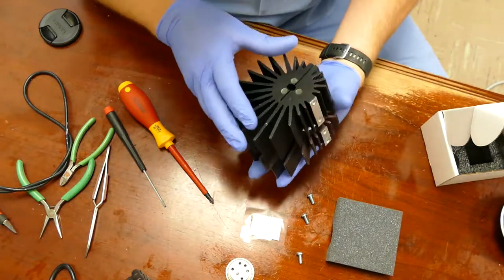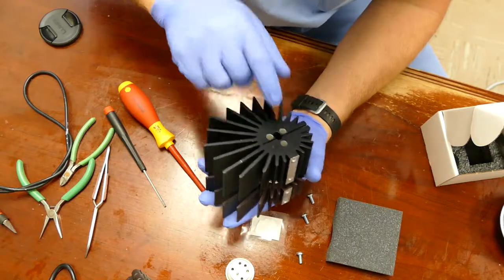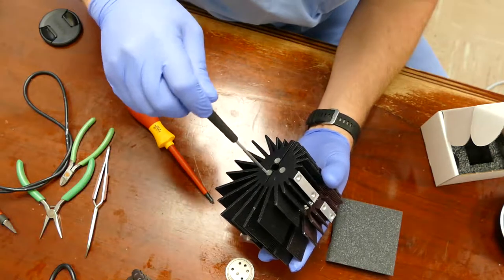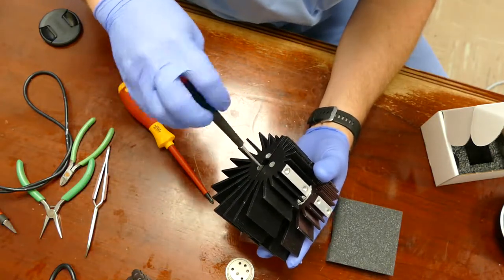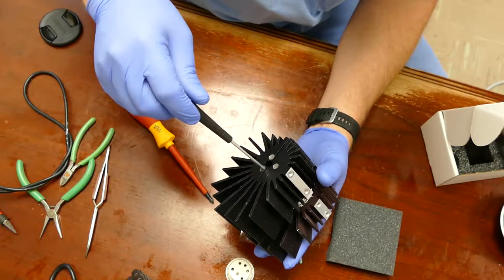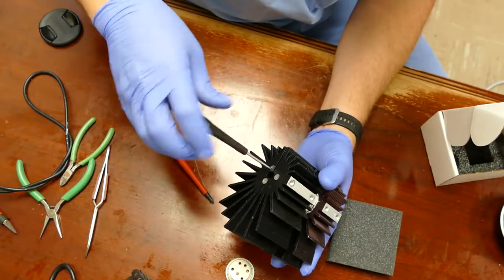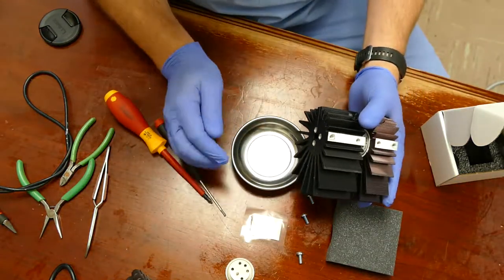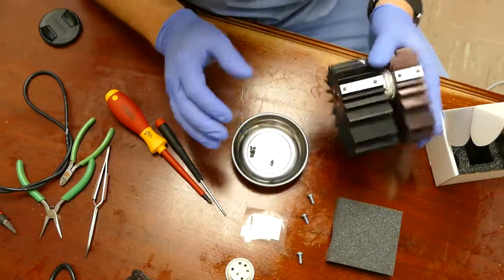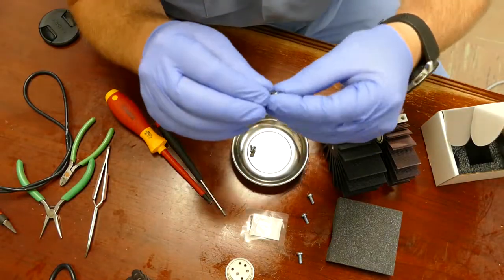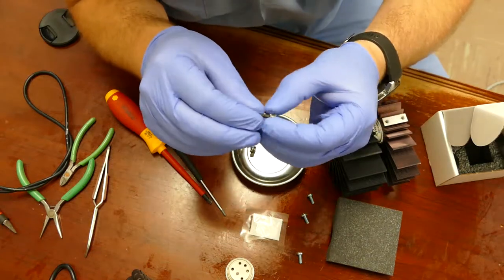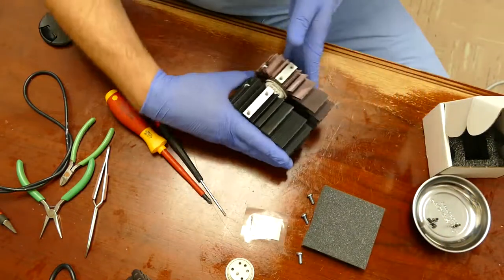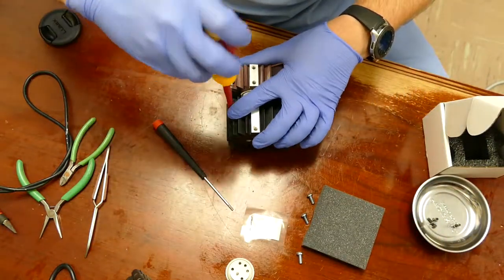Here you can see my two heat sinks. I've got three little screws down here, that's the 7/64ths. I'm going to go ahead and remove those now. And I'm going to dump those into a little tray because, as you see, there's more than just the screws in there. There's a tiny little lock ring, so you want to make sure that you retain those rings. That's why I dump them onto a dish.